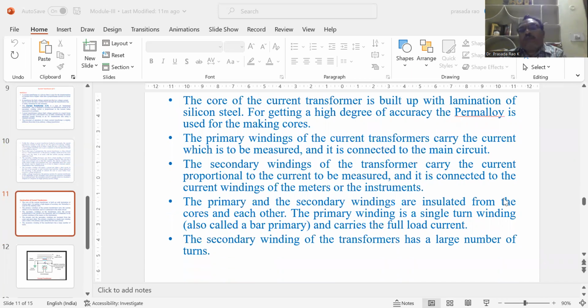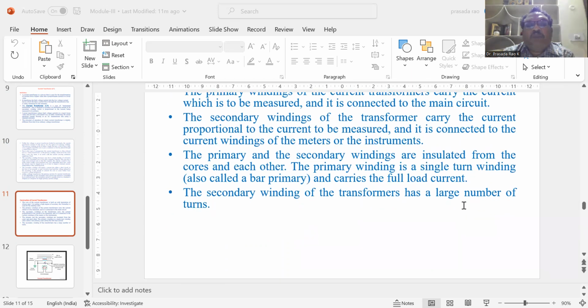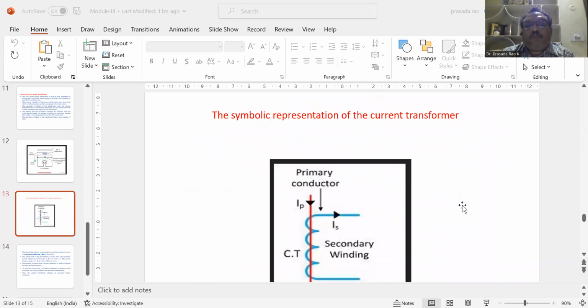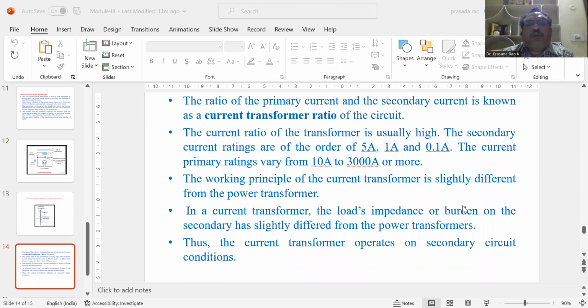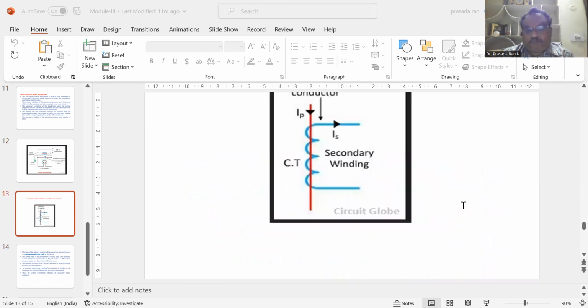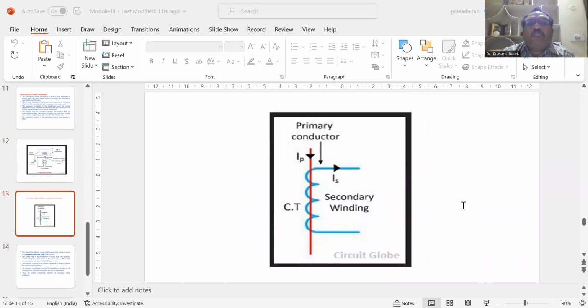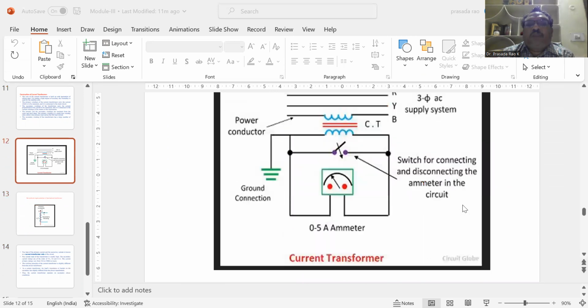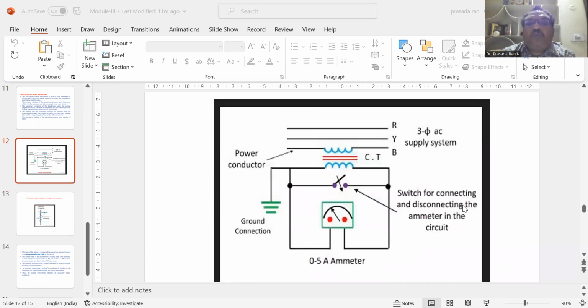The primary and the secondary windings are insulated from the core and from each other. The primary winding is a single turn winding and carries the full load current. The secondary winding of the transformer has a large number of turns, and the ammeter is connected in series to the secondary winding. And this is the circuit diagram for a current transformer.